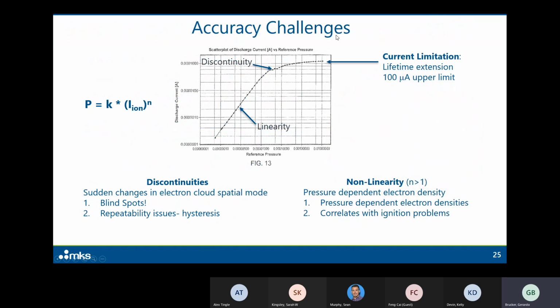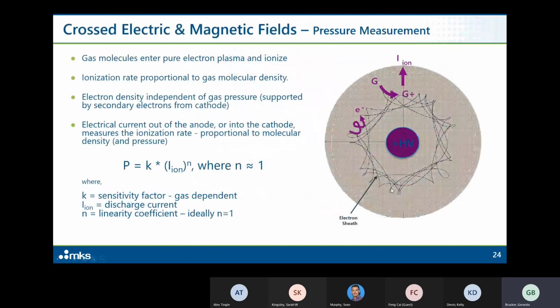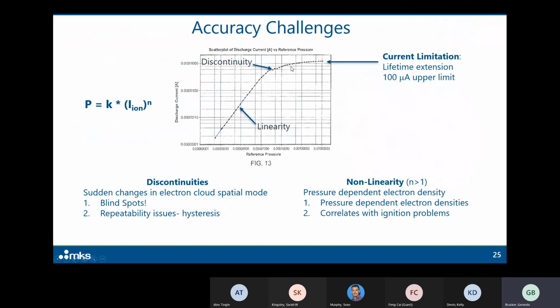Unfortunately, there are challenges when you make a cold cathode gauge. The two known challenges, particularly if you're trying to get high accuracy, are that you've got to achieve this linearity on the performance, and you also have to avoid what's called discontinuities. Going back to this pure electron plasma, depending on the voltage and magnetic field conditions in the system, sometimes the cloud can actually switch to a different spatial mode. And when it switches to a different mode, the sensitivity of the gauge changes, and you get these steps in sensitivity, which affect the calibration.